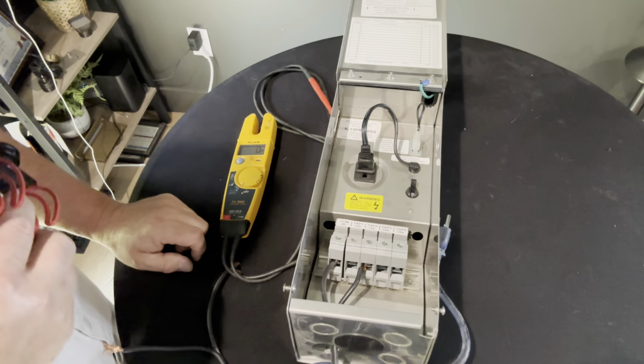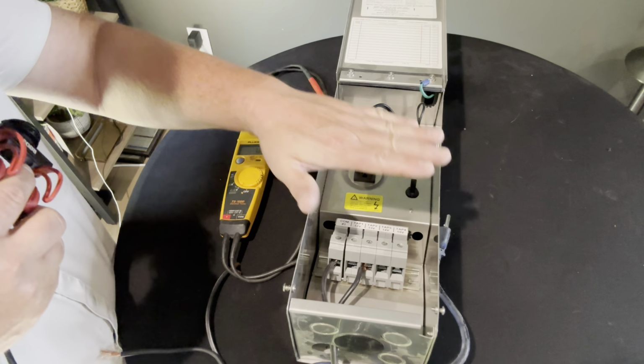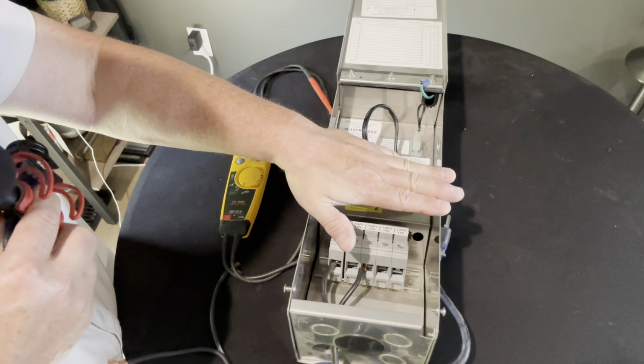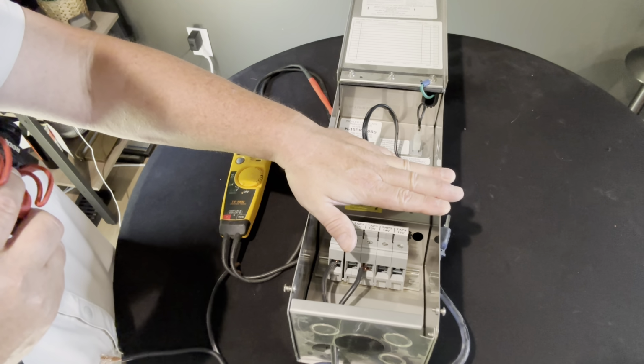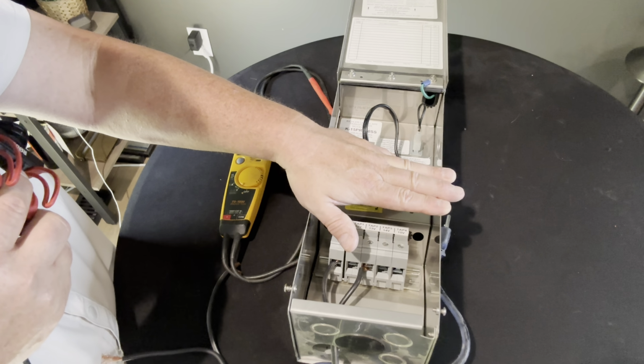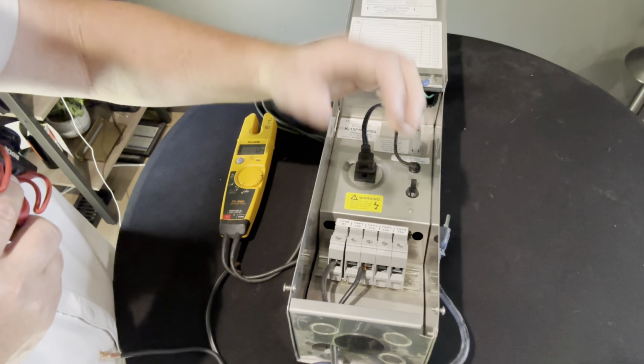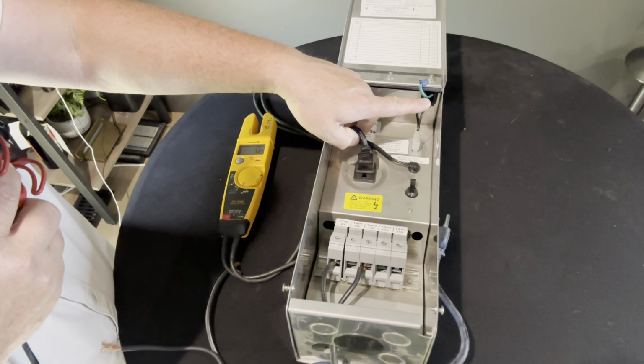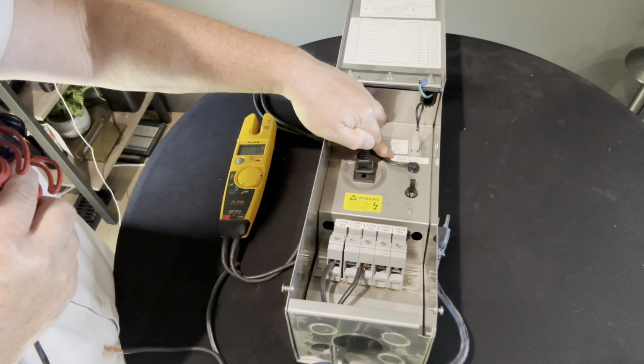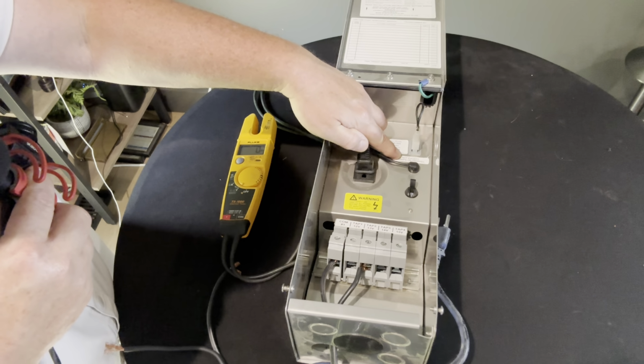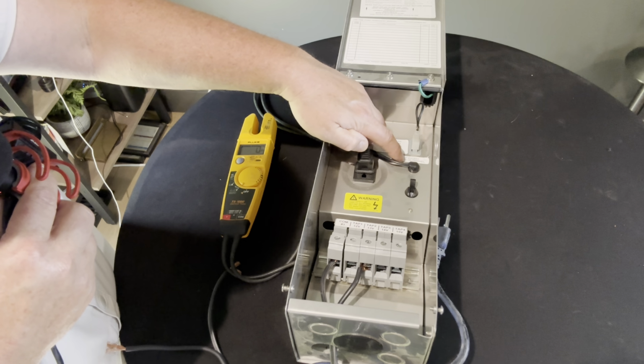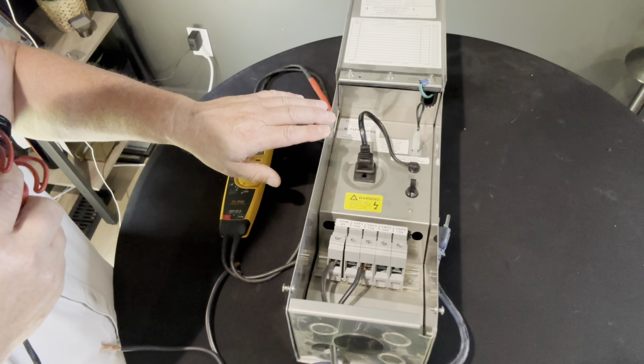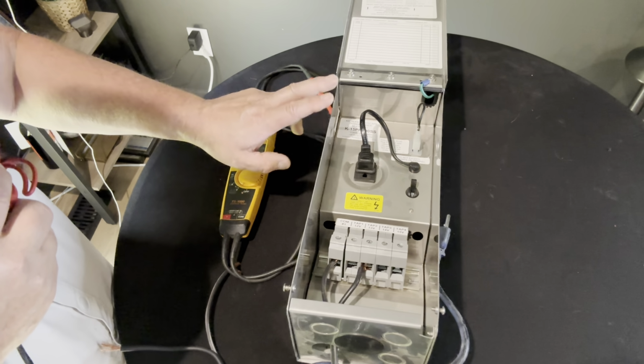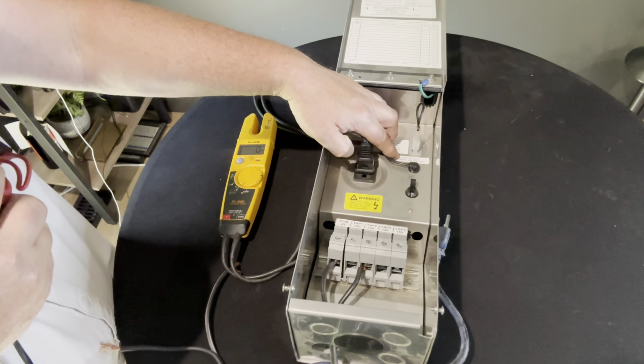Now let's talk about amperage. When there's a load on the transformer, meaning we've got lights on and something pulling from it, if I wanted to test the primary side here, there's a sticker that says do not exceed 2.5 amps on the primary. This is a very common transformer, a 300 watt transformer, and most of them are rated at 2.5 on the primary side.